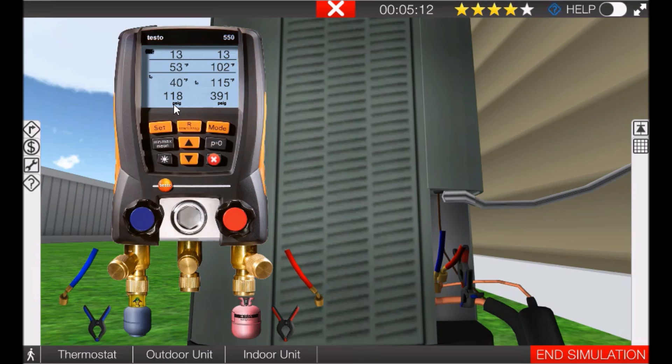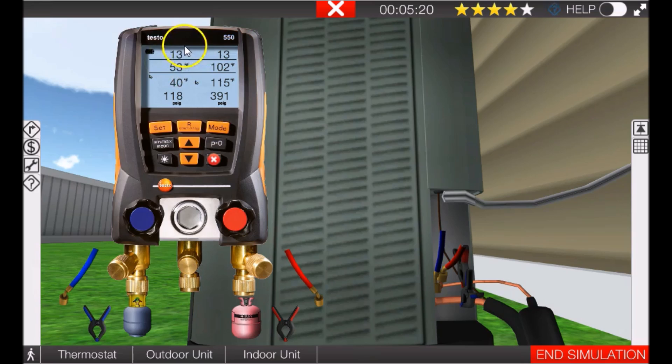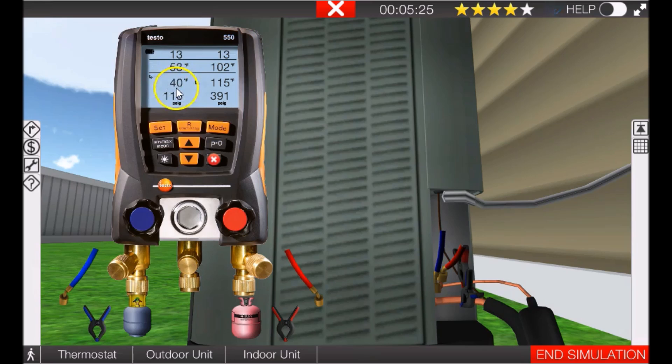You can see that from our notes on that. Now we've gone up to 13 degrees subcooling - this is a TXV system, so subcooling is maintained - but now we're at 40 degrees coil temperature and we won't be freezing anymore. So this is one of the simulations that we have in the course. It does tell you that it is an R410A system.